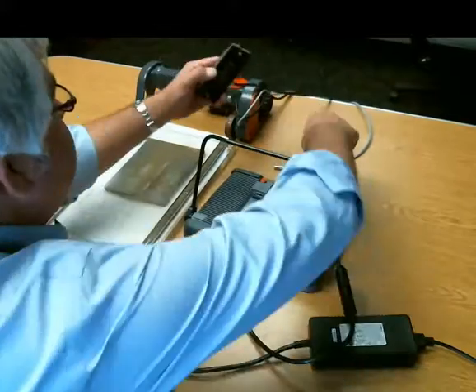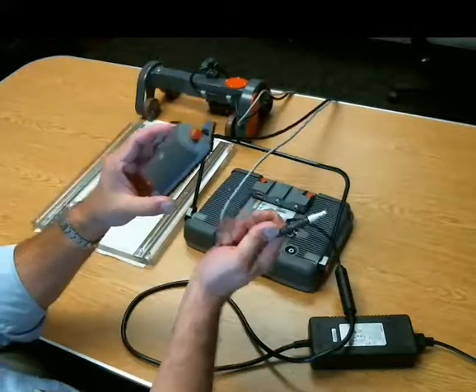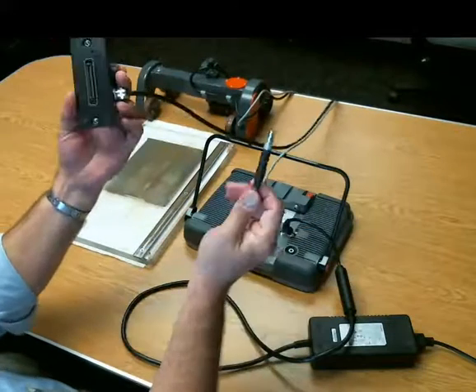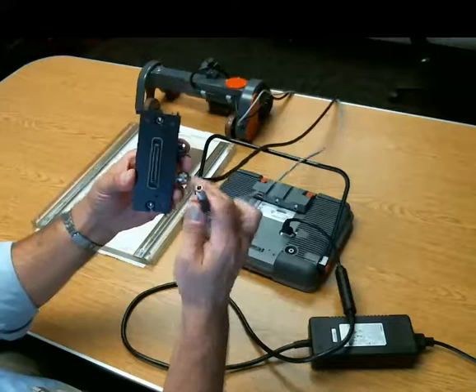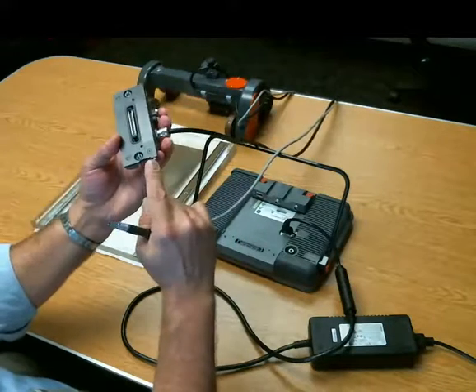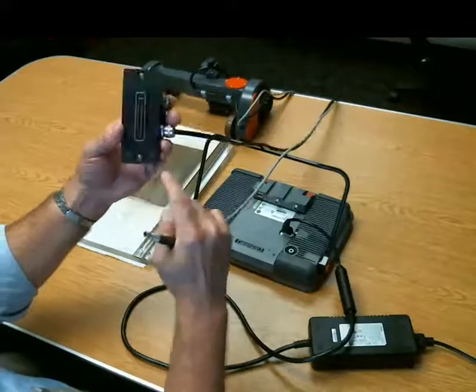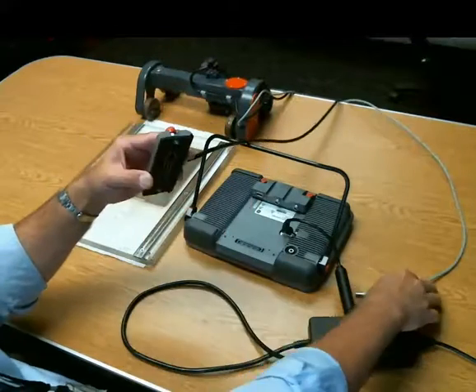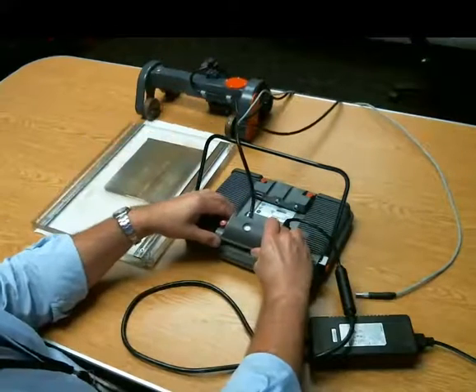To attach the probe from the scanner, you have two connections. Fairly obvious what goes where, I think. With the probe connection, there's a 144-pin docking connector. There are little nibs on each end that are keys that make sure you get it properly aligned.